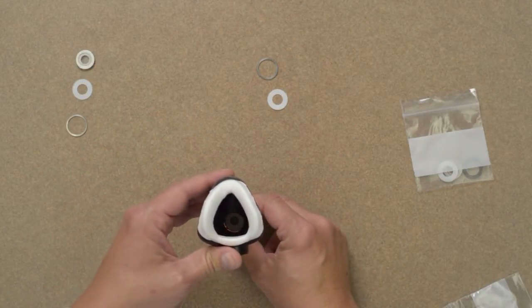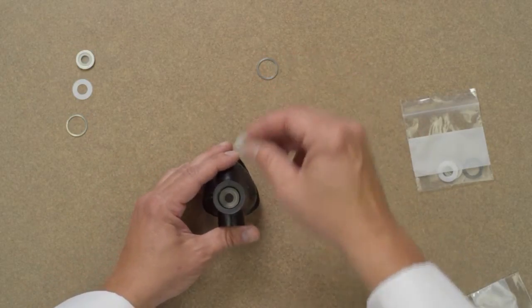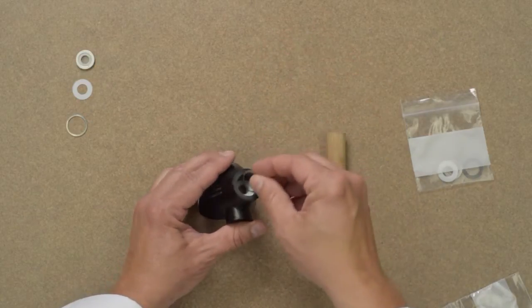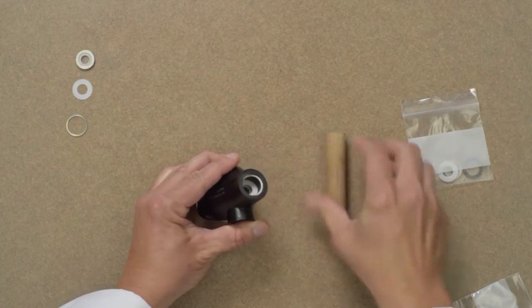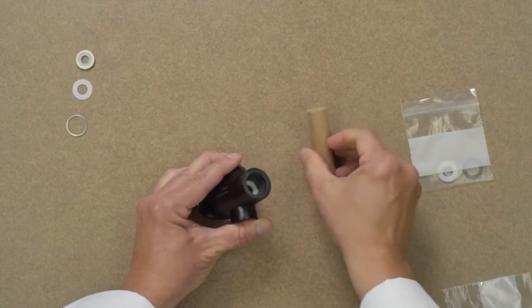Next lower the mask inhale port onto the installation tool and then flip it over. Then set the Teflon washer onto the check valve body. Next push the retainer spring washer into the inhale port at an angle. Once it's in the port then use the installation tool to press the three parts evenly into place.